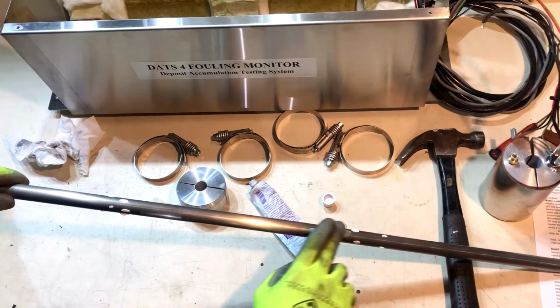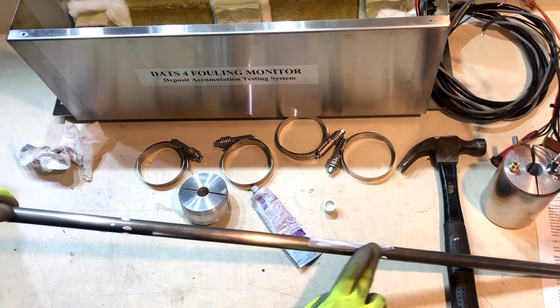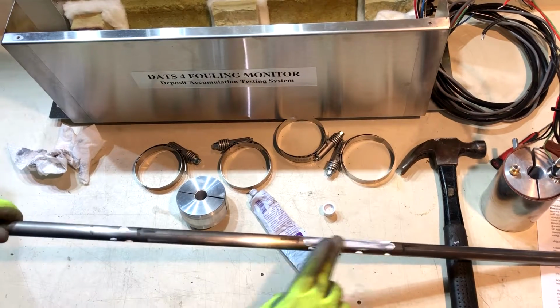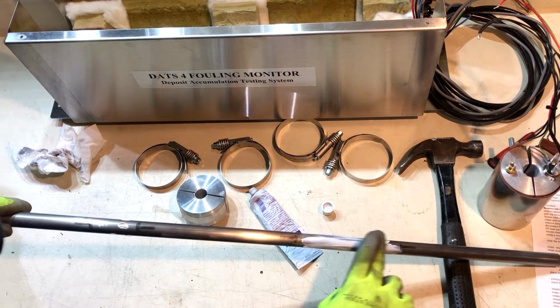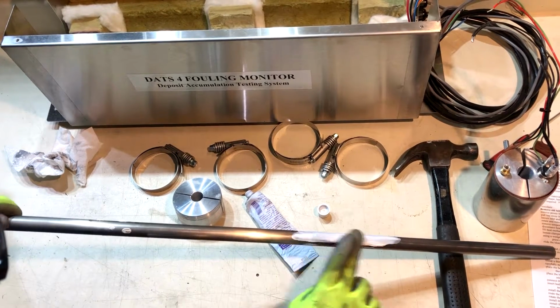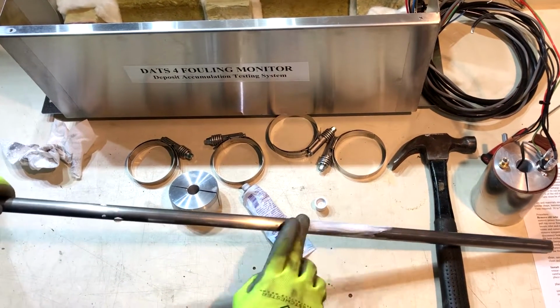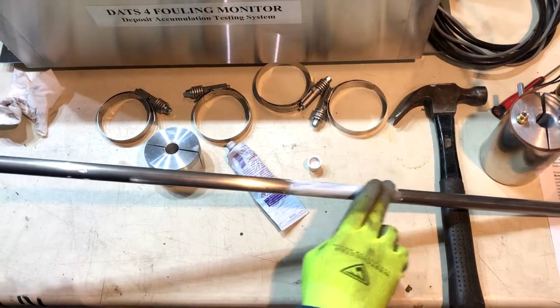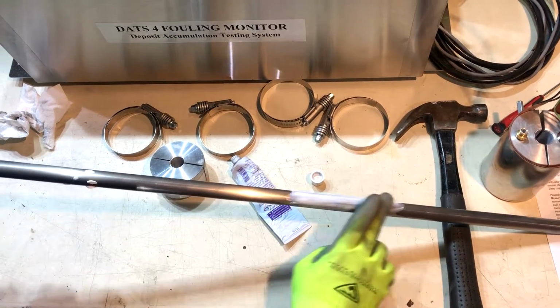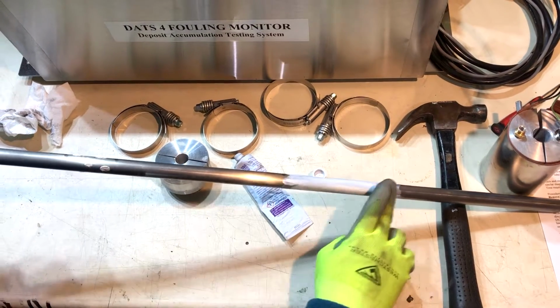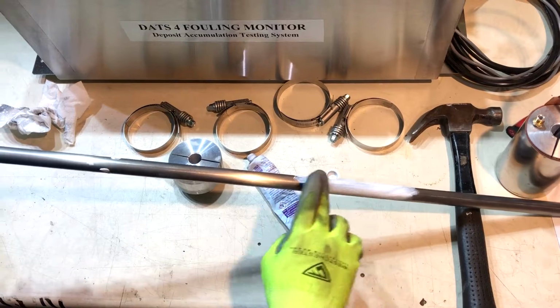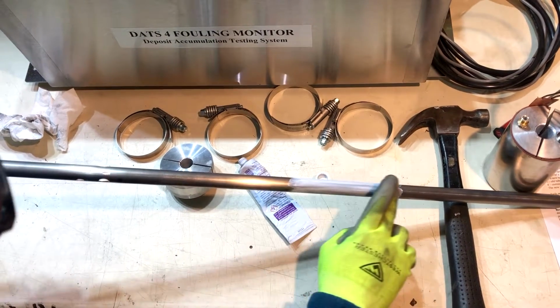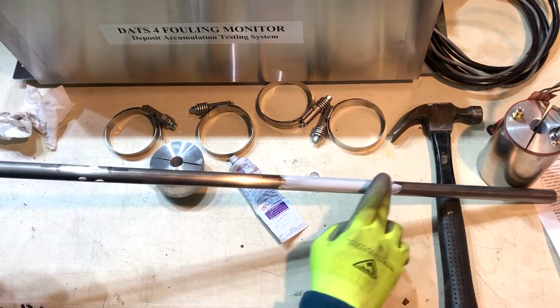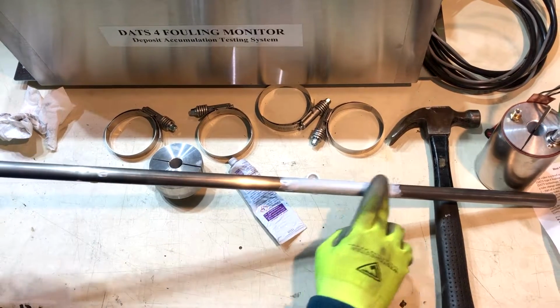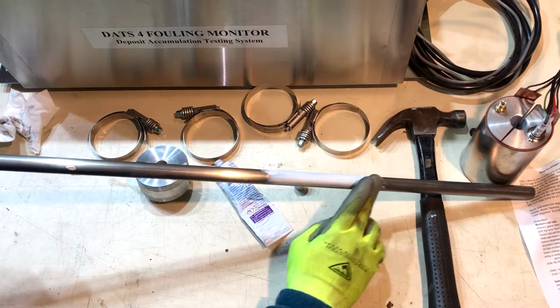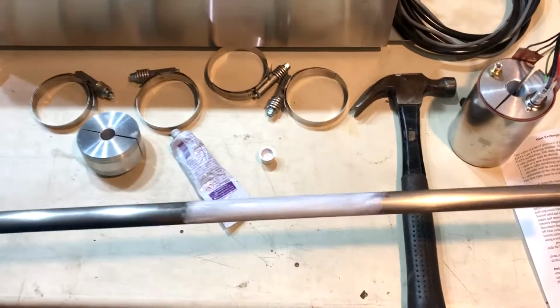To smear this grease, we're looking for just a translucent layer of material beneath the heater block itself, and a little over either edge is fine. And you'll note why we've got the markings for the inlet and heater block a little bit wider so that we can ensure we've got the proper location and full coverage. This is important to get this material on the right thickness and that the tube is blemish free, particularly in this area, so that the temperature of the block is stable and uniform. So that is about what it should look like before clamping.